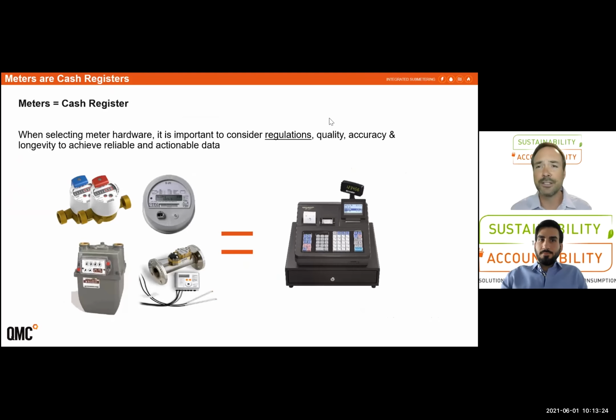And before we get on how to design the system, one really important thing to remember about a meter is the majority of them that are deployed in the field are cash registers. They are there primarily to be the medium of exchange of a utility between the provider, like a local utility, and the customer, whether it's a building or a sub-metered tenant. And so the requirement primarily is for billing. And then we obviously want to use that same data for energy management commissioning purposes as well. And there's a whole other group of meters that are for energy management only, which don't have the same restrictions on them as revenue grade systems do.